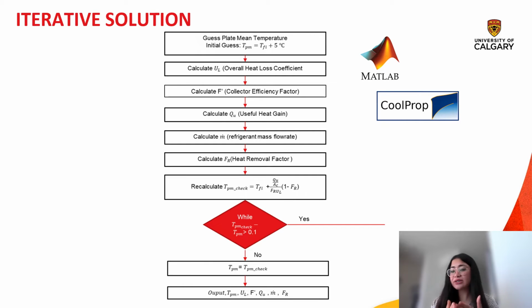So the only reasonable approach was to develop an iterative solution to our system of equations in MATLAB. The code extracted the thermodynamic properties of our refrigerant from the CoolProp library and allowed us to iteratively solve the Hottel-Whillier equations. The converged solution, though not a transient state analysis, provided an estimate of the system's performance in terms of theoretical useful heat gain of the collector and the theoretical coefficient of performance, or COP, of the heat pump cycle—essentially how well our system moves heat from one location to a more useful one.